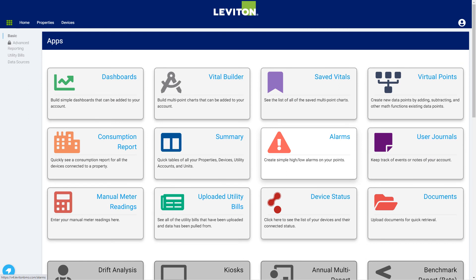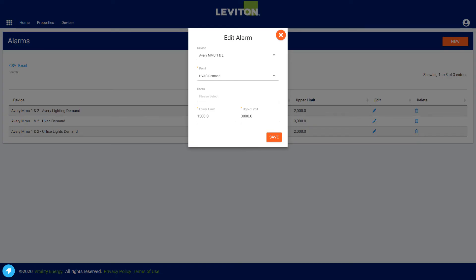It may also be useful to use the alarms feature to send email notifications when there are unusual readings coming from the system. Setting up the alarms is quick and easy — just fill out a short form with the appropriate device and point, setting the upper and lower range limits. Select the user that the email alerts will be sent to, and any time there are readings outside the limits, the system will automatically email an alarm notification to that user's email.